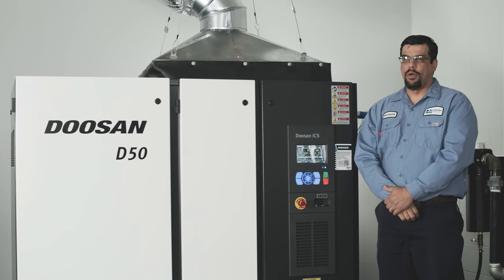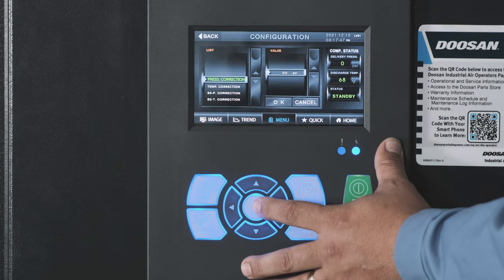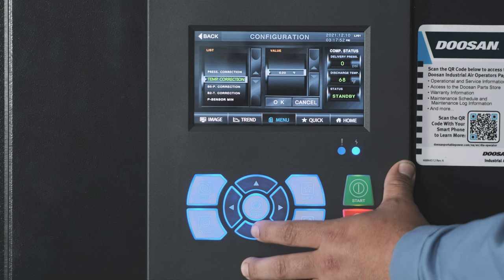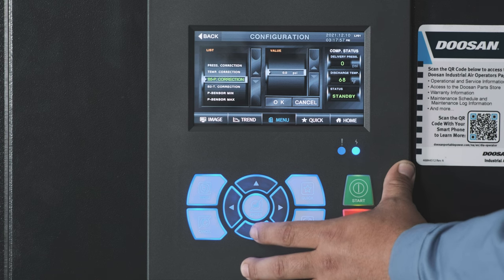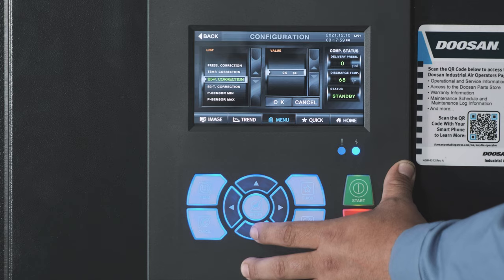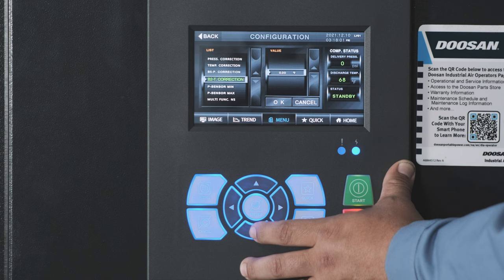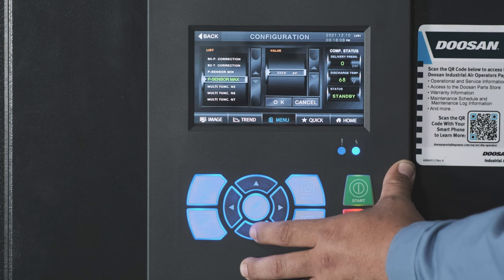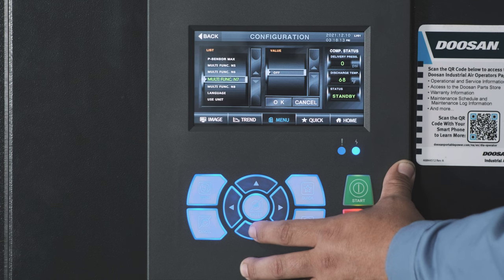The configurations menu allows the user to view the following. Pressure correction: offset for pressure transducer calibrations. Temperature correction: offset for temperature calibrations such as discharge temp. Your B5P is the separator tank wet pressure, if equipped. B2T is your ambient temperature. Min and max pressure of transducers. Multifunction outputs N5 through N8.